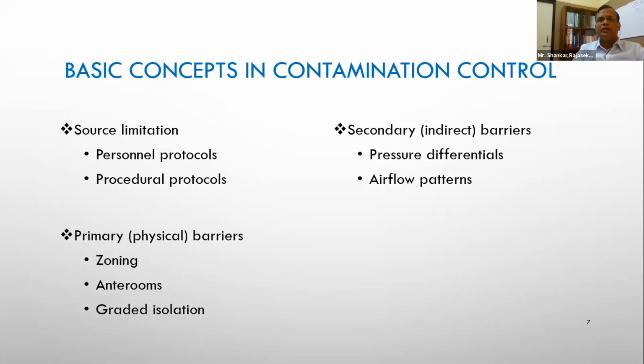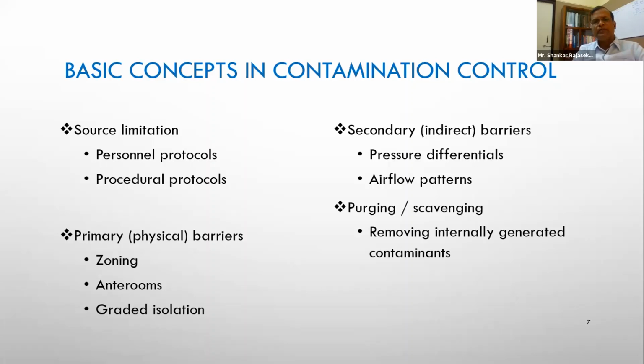So we prevent contamination and infection by using pressure differentials in critical areas. We use airflow patterns. We make the air move in a particular way so that the most critical part of the procedure is given the maximum amount of protection. When I'm talking about purging and scavenging, not only is the air that we bring from outside carrying infectious agents, but there could be internally generated contaminants also, because of so many people doing so many activities inside the space, which need to be scavenged and removed in real time. Otherwise, that concentration will keep on building up. So you will have to keep removing them on a real-time basis as and when they get emitted or generated.